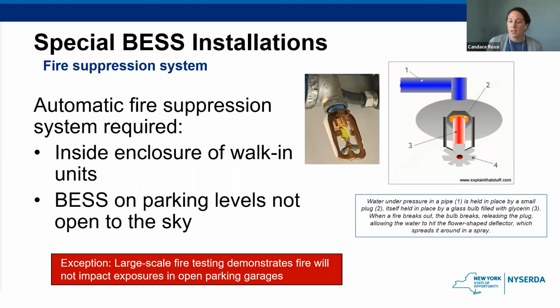So here we have the fire suppression system requirements. Basically, an automatic fire suppression system is required if it's inside the enclosure of walk-in units, or for battery energy storage on parking levels not open to the sky. I think you can recognize that if this is in a parking garage, but on the top level and isn't covered with a ceiling, it might be hard to utilize the ceiling as part of the fire suppression system. So you might need to make sure that it's inside the enclosure instead.